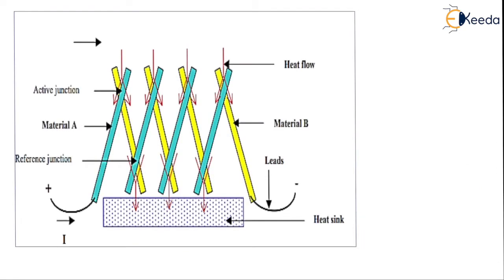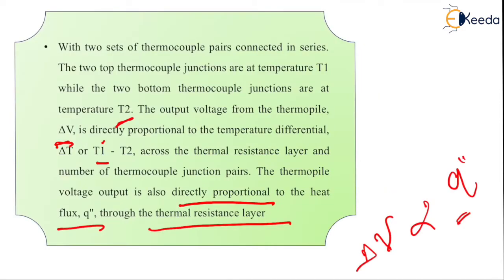Again, you can see in this diagram the array of thermocouples which is formed to produce a thermopile. The blue color shows material A type, and the yellow color shows material B type. This is the positive lead, this is the negative lead, and between these two leads you have to measure the total output voltage, which is proportional to the heat flux Q.